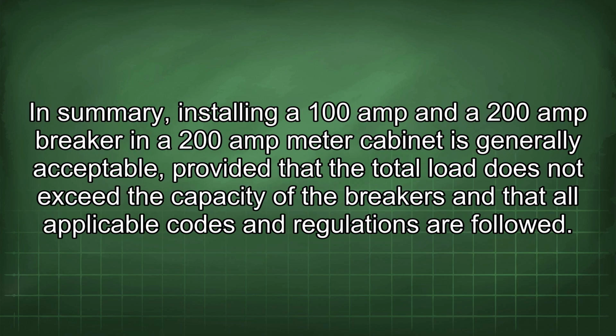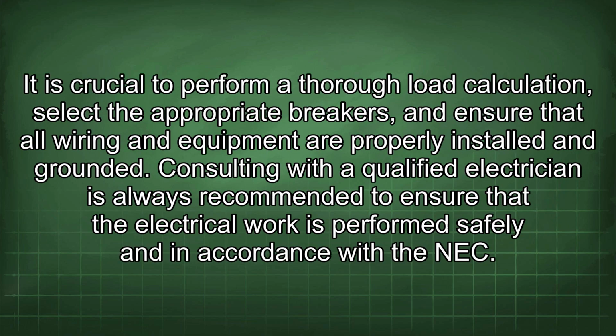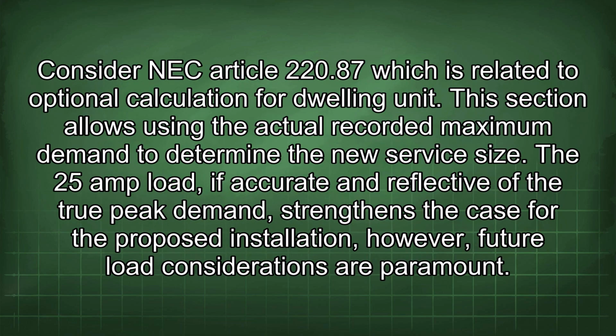In summary, installing a 100 amp and a 200 amp breaker in a 200 amp meter cabinet is generally acceptable, provided that the total load does not exceed the capacity of the breakers and that all applicable codes and regulations are followed. It is crucial to perform a thorough load calculation, select the appropriate breakers, and ensure that all wiring and equipment are properly installed and grounded. Consulting with a qualified electrician is always recommended to ensure that the electrical work is performed safely and in accordance with the NEC.